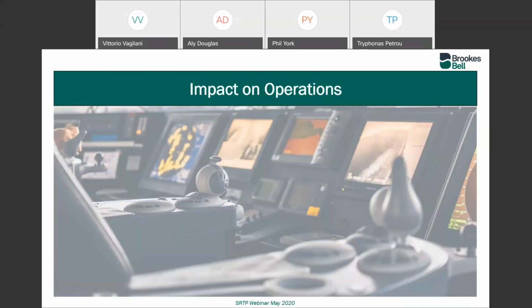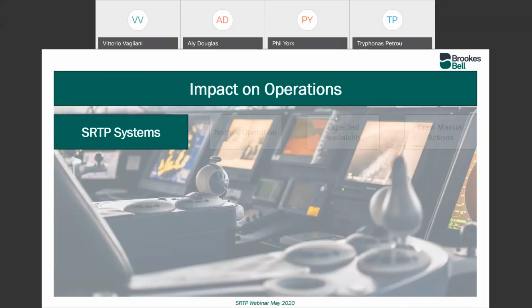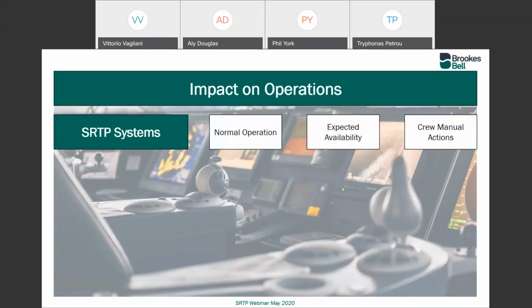So what does it mean in terms of operations? In terms of operations, obviously we now have these systems which have been marked as being the safe return to port systems, and the crew need to understand how to carry out normal operation. This may not be that different from normal operation had the system not been designed to meet safe return to port. But it is important that they understand what is the expected availability, so that in the event of an incident, they understand what's an acceptable loss versus what is an unacceptable loss and therefore requires crew manual actions.